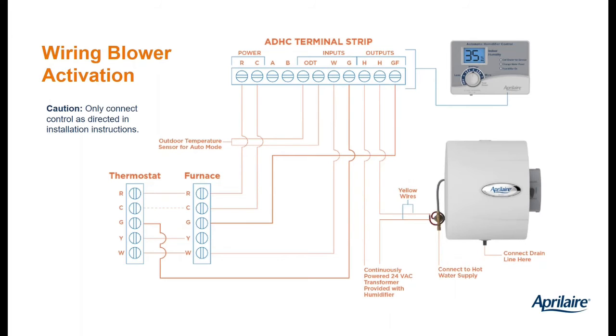Let's skip the G's for a second. We'll come back to those. Let's look at the H's. On the output section, you've got 2 H's. Remember, this is providing a dry contact when the humidistat wants the humidifier to run, and our evaporative humidifiers need 24 volts to run. So all we need to do is create a big series circuit that's going to be composed of the 2 H terminals, the 2 yellow wires on the solenoid valve, and then the 2 screw head terminals on your 24-volt transformer. So again, just a large series circuit.